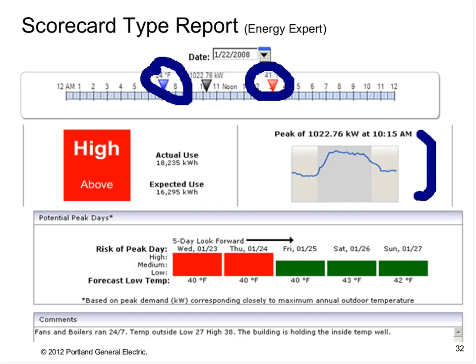This right here is, I think, pretty important. If you look at it, you'll see a load shape, and then you can see that the gray block in the middle is actually meant to be the hours of operation. So if you see the left edge, that would be their startup time. They hit that perfectly. However, it looks like they did not hit the nightly edge, and it took them longer to shut down.